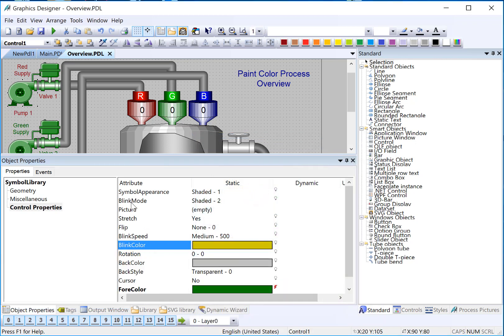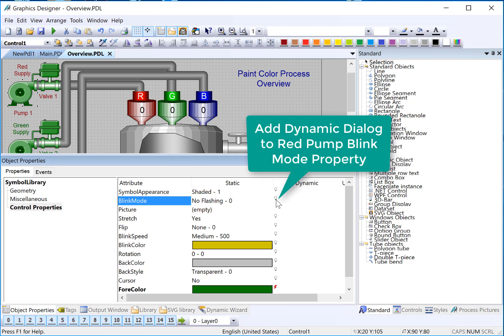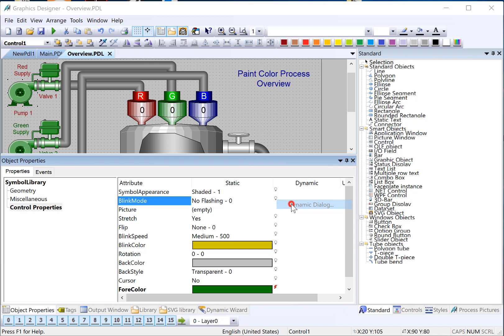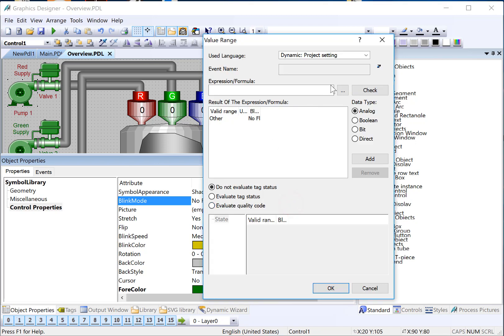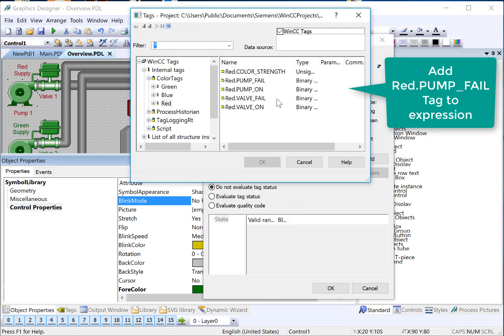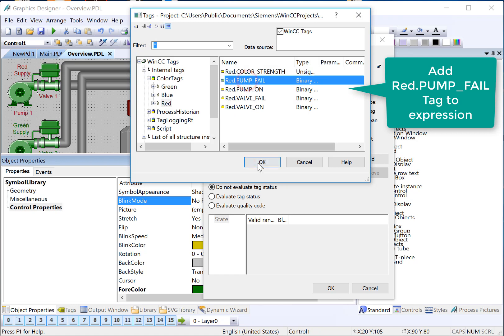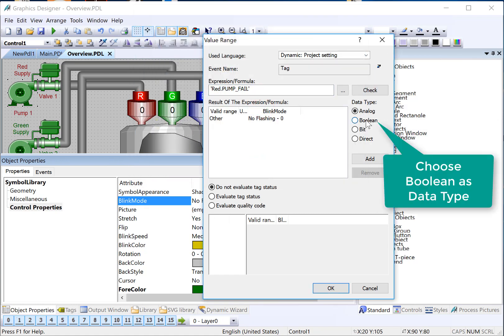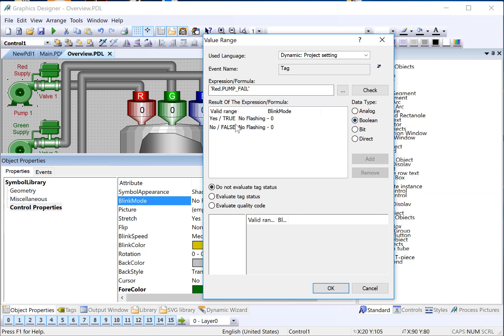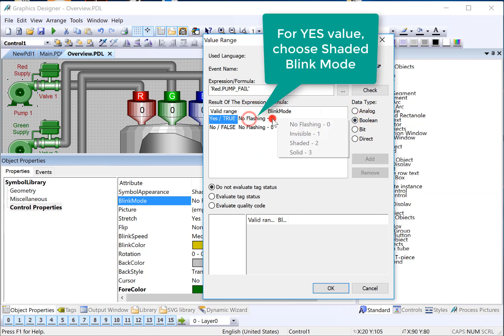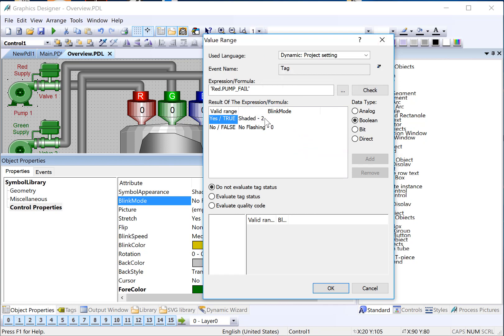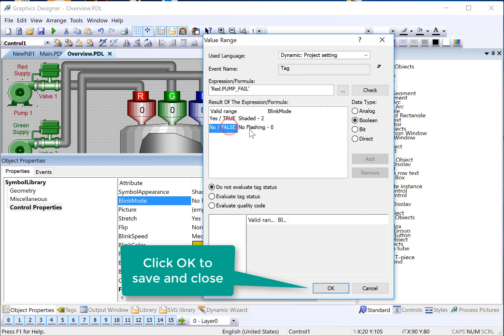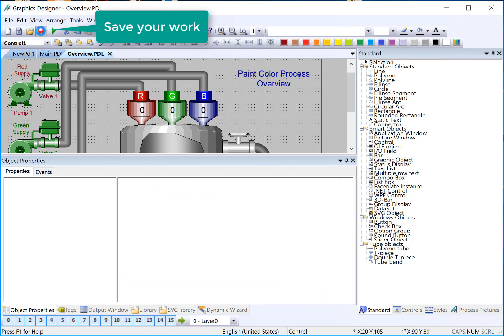And then for our blink mode, I'm going to set it back to no, but I will right click through dynamic dialog on the blink mode. We're going to look at our red pump fail. And it's also going to be binary. So we'll choose Boolean. And if it is failing, then I can just double click here and say, go to the shaded mode, which is going to make it blink between whatever color it happens to be in the blink color. And if fail is a zero, meaning there's no failure, then it's just not going to flash. I'll save this.